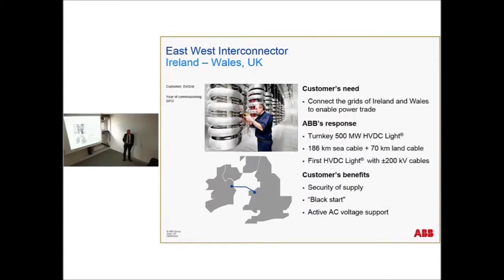The last one that we took in service this summer was a 500 megawatt connection between Wales and Ireland. It connects Ireland and UK for trading of electricity, and also to support the future wind parks to be built on Ireland. So we will support the frequency and the voltage here by this HVDC light system. Also possibilities to have black start if you have an outage in this area.